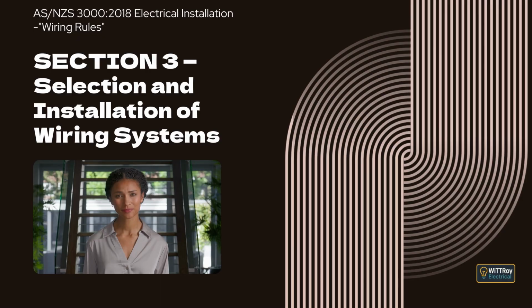Clause 3.9.9.2, Precautions. This clause explains that appropriate materials and installation methods must be used to reduce fire risk, and that fire-rated cables may be installed without additional precautions where suitable. Clause 3.9.9.3, Penetration of fire barriers. This clause explains that where wiring passes through fire-rated building elements, openings must be sealed, fire ratings reinstated, and sealing systems must resist fire, smoke, water, and combustion products.